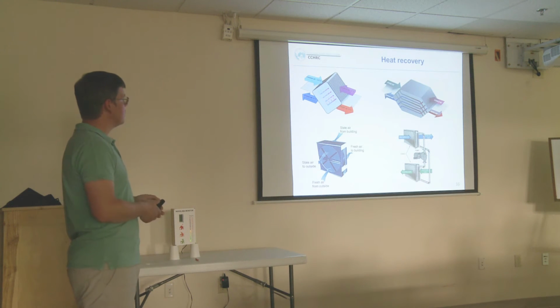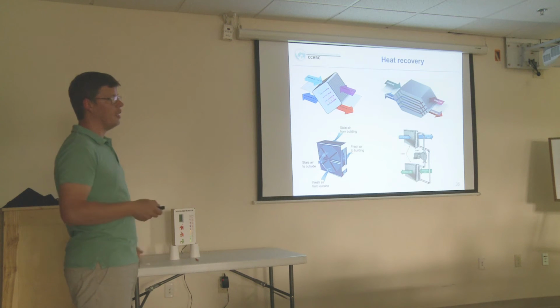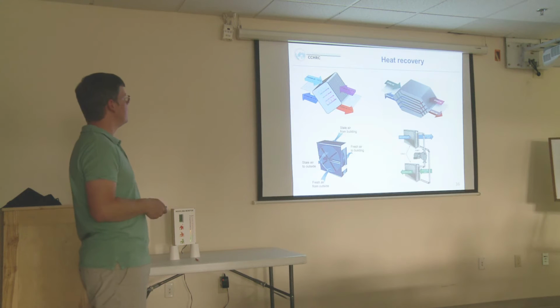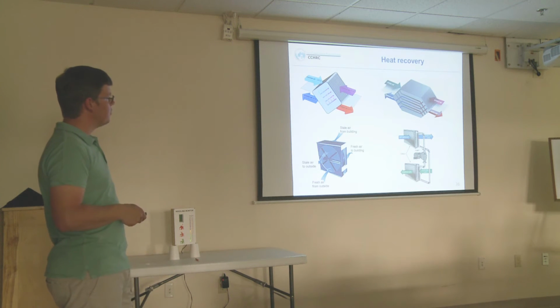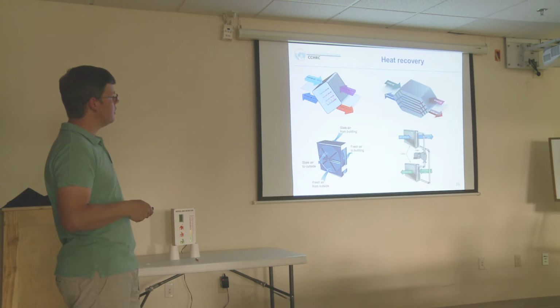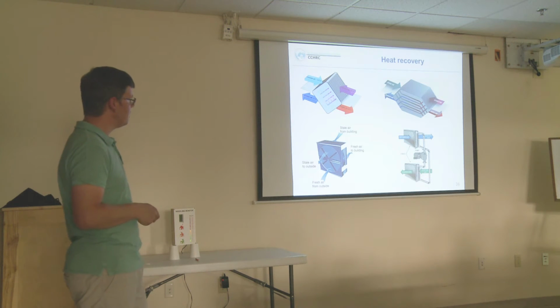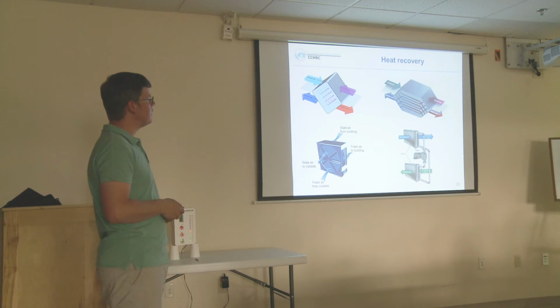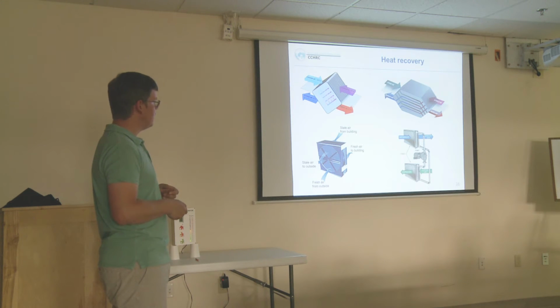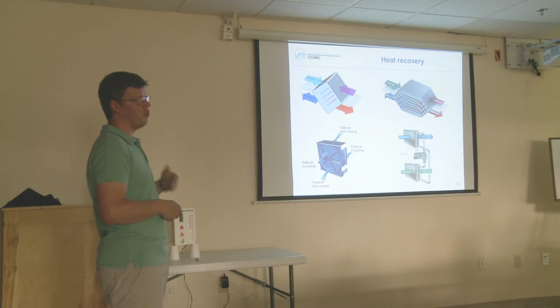And then the third type is a coil heat exchanger. That is not used in small units that much. It could be used in large applications, because it's complicated and requires a pump to circulate glycol from the cold coil to the warm coil. The advantage of this one is that we can regulate the speed of the pump and that way regulate the efficiency. So, as we're going to talk about later, the freezing problem can be avoided by this. The same applies for the rotor, because we can vary the speed of the rotor, and that way we can regulate the efficiency of the heat exchange.